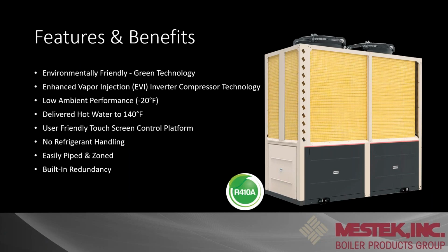Green technology, environmentally friendly. We have an enhanced vapor injection EVI inverter compressor, which I can get into a little bit. So just to give you an idea of what EVI is. EVI is used to achieve a higher performance at a lower ambient temp. Okay, so the EVI is designed for cold climate heat pumps. And just to give you a quick rundown, it uses a third small internal plate heat exchanger, which is called an economizer, within the refrigerant cycle.